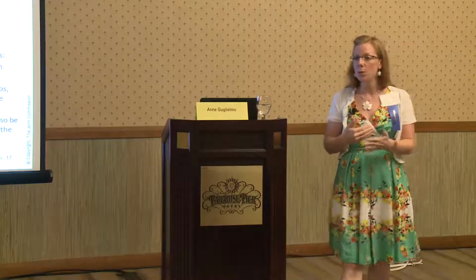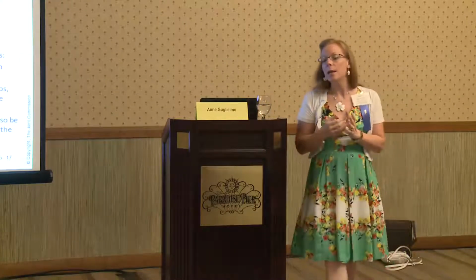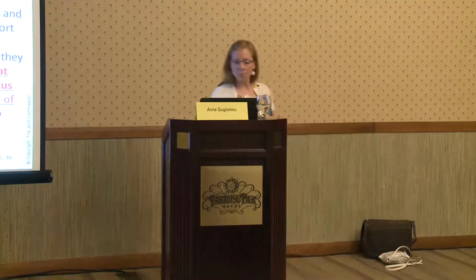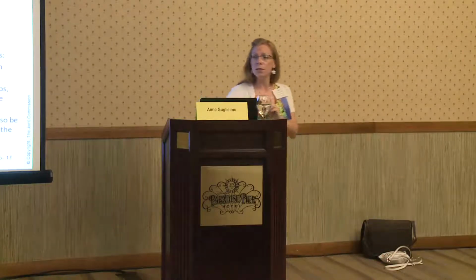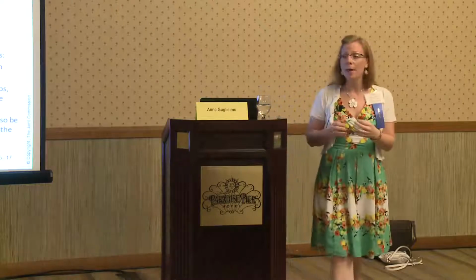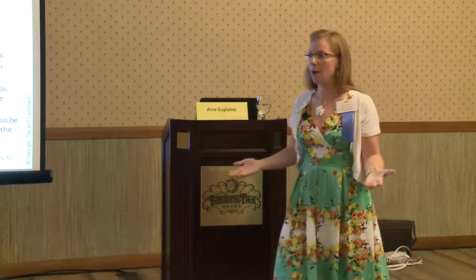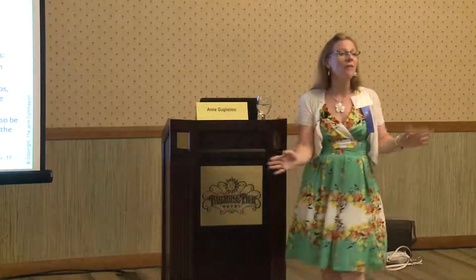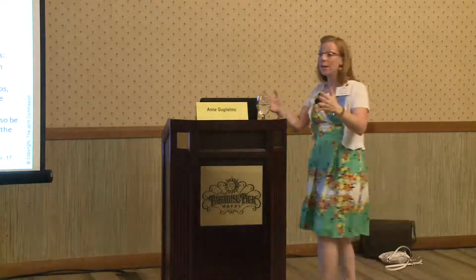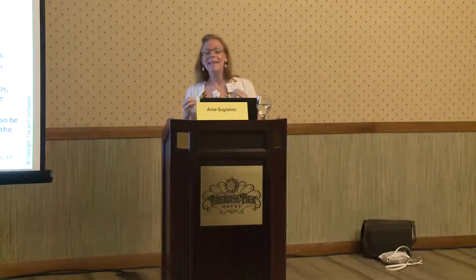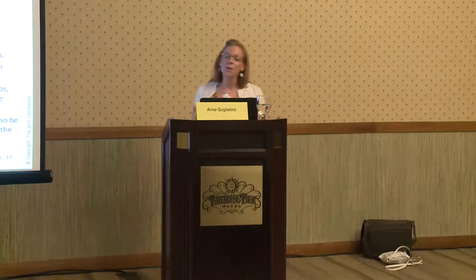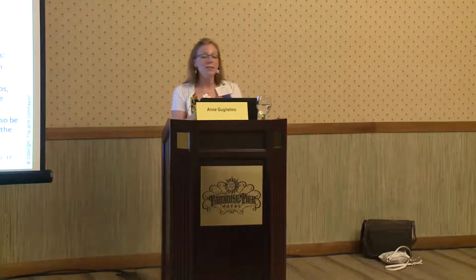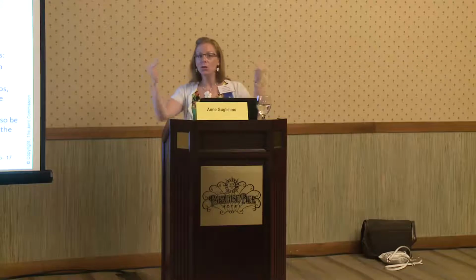When these new standards broke and we said that we had an EP where you have to identify the operating components of your utility system, I can't tell you how many people came back to me and said, well, this is nuts and bolts and wires and conduit. Whoa, whoa, whoa, way too far. We're not looking to have you take it all the way. But it can't operate without that component. Yes, I get that, okay? But we want you to look at things that are going to have performance-related criteria and a measurable outcome. Take a look at it from that level and don't go too far down.